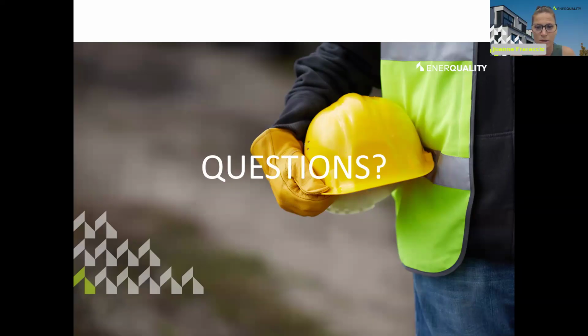Okay. I'm going to read out one more question, then I'm going to do a little wrap up, but we'll keep doing questions right after that. So Jeff had asked, can it be installed horizontally? Is the performance the same? So the performance, as I mentioned earlier, goes down significantly when we go from vertical to any other angle. We found that if you install it horizontally, on the plumbing side of things, if you look at drainage, everything's fine. There's no issues or concerns. But in the performance, we usually drop to about 30% of the rated performance. So if we have a 60% unit, then we'll go down to about 20%.